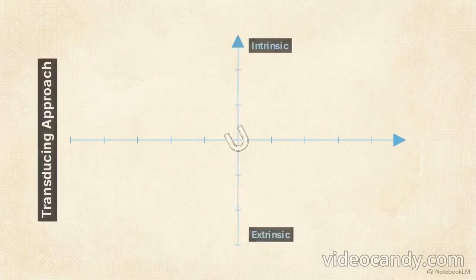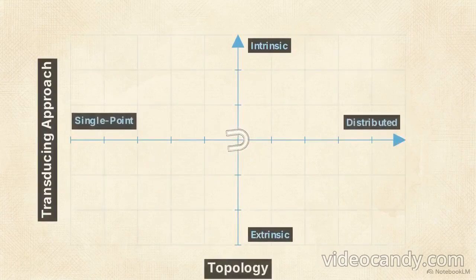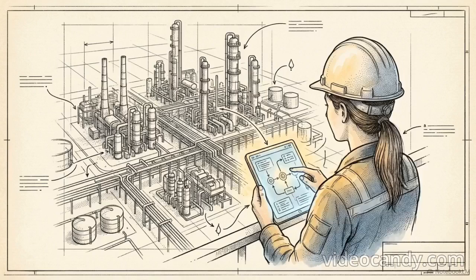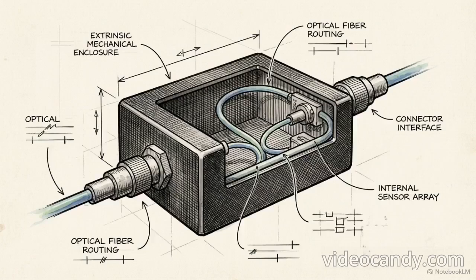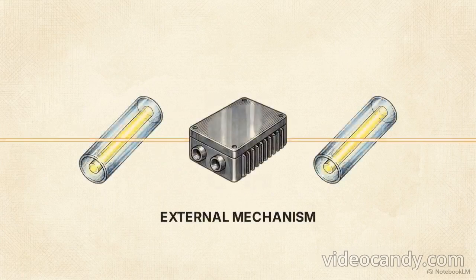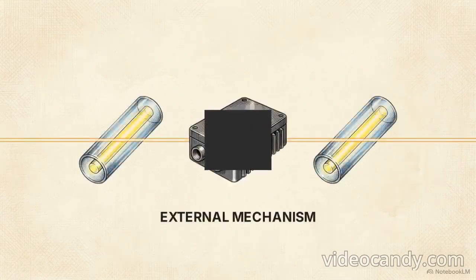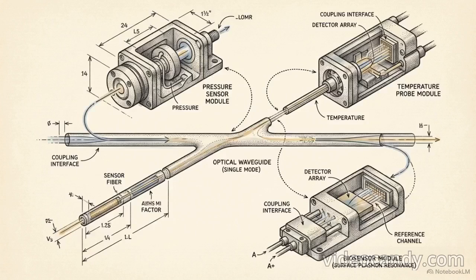To organize these variations, we classify fiber optic sensors along two primary axes: the transducing approach, which dictates how the light is modulated, and the topology, which dictates where the sensing physically occurs. Navigating this two-axis framework is a strict requirement for architecting a sensor network tailored to a specific harsh environment. The first major categorization on our transducing axis is the extrinsic or indirect approach. In an extrinsic system, the fiber functions strictly as a waveguide, carrying light to a separate external mechanism. Inside this device, the light beam is physically manipulated. Mechanical shutters, chemical reactions, or physical gaps alter the beam in response to the measurand.